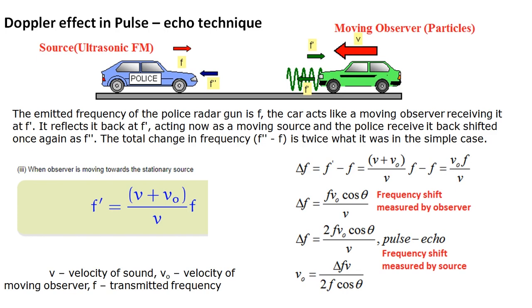The frequency shift delta f is calculated as f × v₀ × cos θ / v for the case where the observer measures it. In the ultrasonic Doppler flow meter using the pulse echo technique, the transmitter itself acts as both source and observer, so the shift is doubled: delta f = 2 × f × v₀ × cos θ / v. From this we derive the flow velocity v₀ = delta f × v / (2 × f × cos θ), where f is the transmitted frequency and v is the velocity of sound.